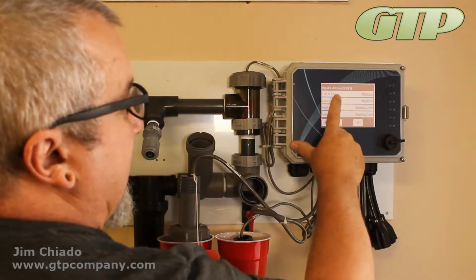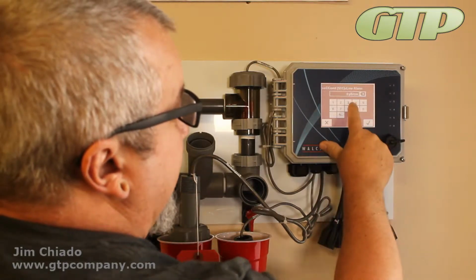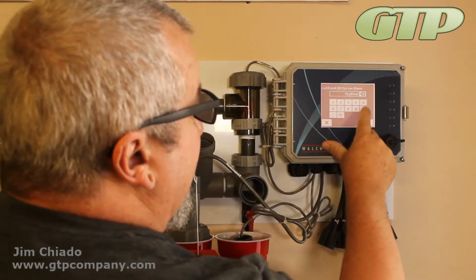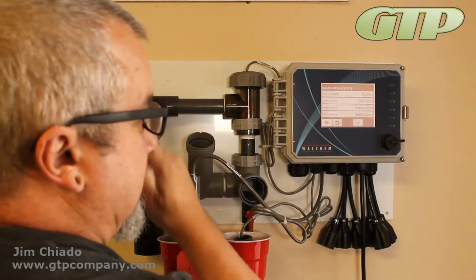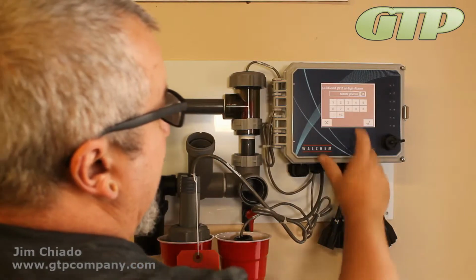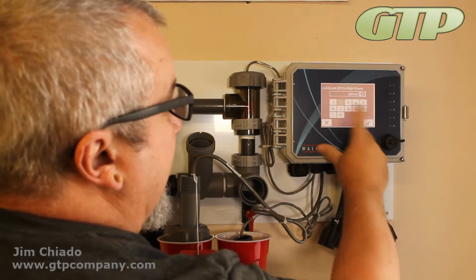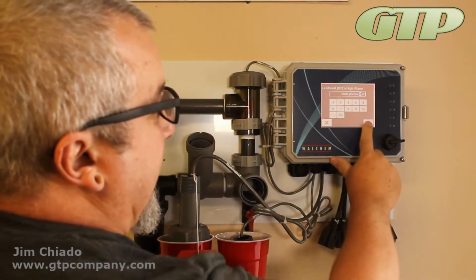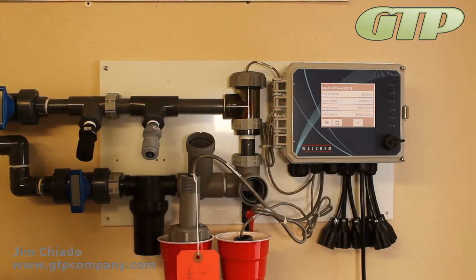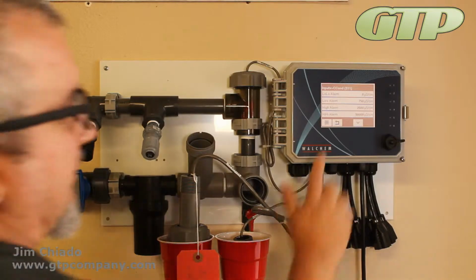Not necessarily for the customer's sake, but for you, and if you're alarming, especially like the low alarm, you may want to set it, let's say we're setting this to 750. And then we're going to set the high alarm. If the valve gets clogged or whatever, and if it ever reaches like 1,500, maybe 2,000, let's say 2,500, then it goes into alarm and it sends that alarm off to me on my internet or my Ethernet, however we decided to communicate with it. So that's really why you would want to set those.